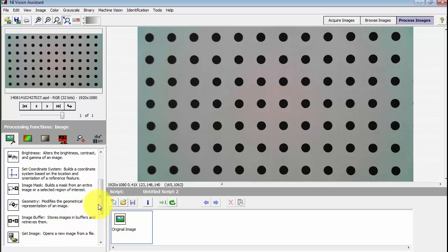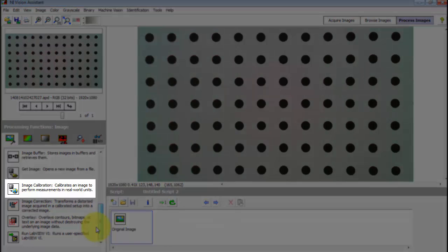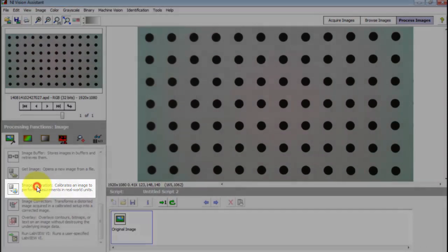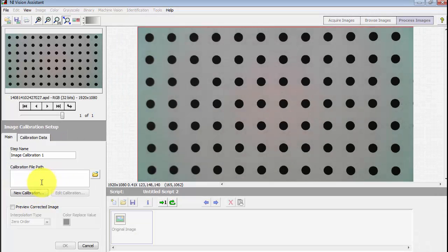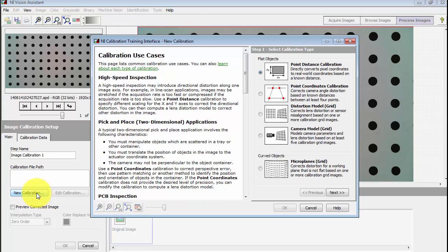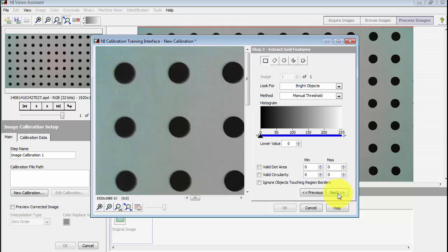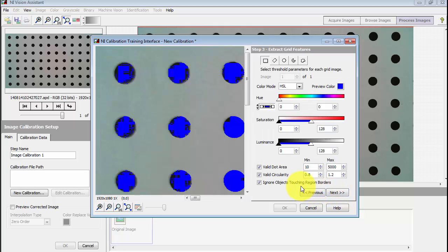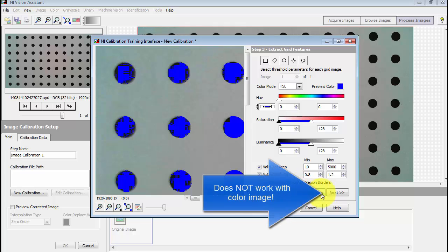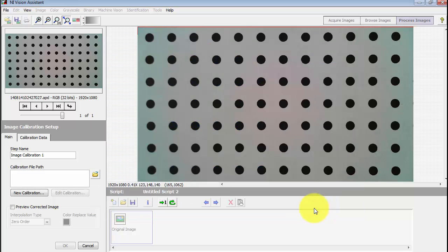Right, looking for image calibration. Let's go ahead and click on that step. You say new calibration, and we are doing the distortion model. Go ahead and click next on that. Next one more time. And when you see a picture like this, it's not so obvious, but this tells you things aren't working properly. The grid calibration only works with grayscale images.